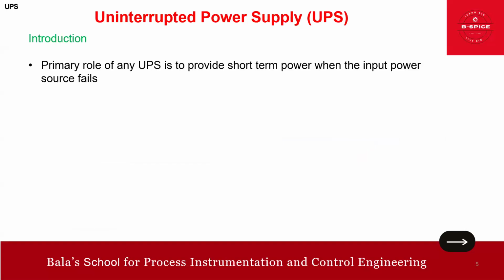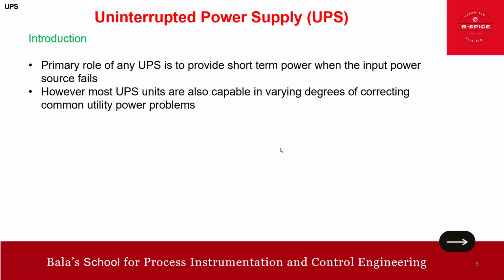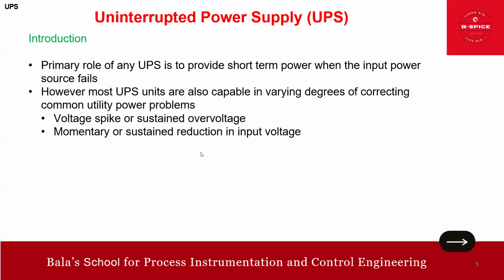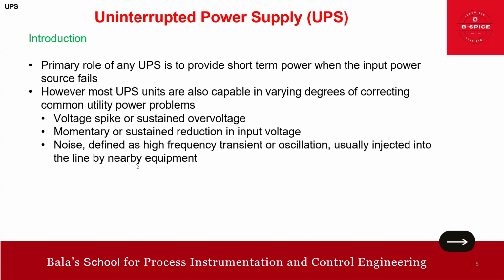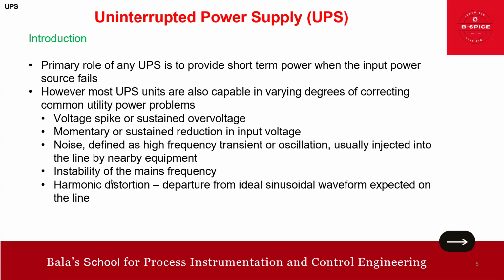That's a point. Now the primary role: to provide short-term power when the input power source fails. However, most UPS are also capable in varying degree of correcting common utility power problems, like voltage spikes, sustained over voltage, momentary or sustained reduction in input voltage, noise defined as high frequency transient or oscillation usually injected into the line by nearby equipment, instability of the main supply frequency, and most importantly, the harmonic distortion.